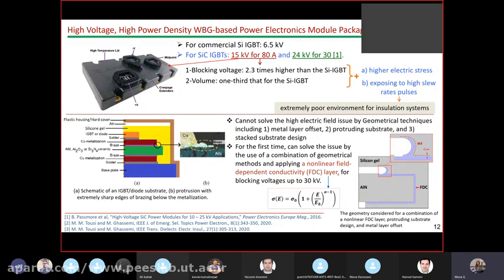You don't see it here, but I can tell you the volume is one-third of that for SI IGBT. That translates into higher electric fields, and also these SiC power modules expose insulation systems to higher slew rate pulses, meaning an extremely poor environment for the insulation system. So there is some work we did here.